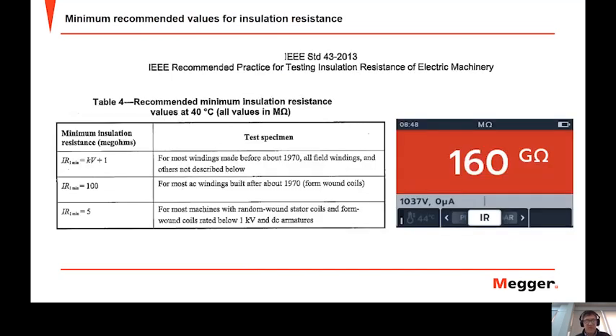So we know what voltage to apply, but what is a good or bad IR value? Well, depending on the age of the winding and also the type of the winding, the value changes. If we only consider modern motors today, and that's sort of after 1970, then we're looking at these second and third column or row. So we can see that for AC windings built after 1970 but form wound, then the minimum IR value should be 100 megohms, and that's at 40 degrees C. So we have to make that temperature correction.